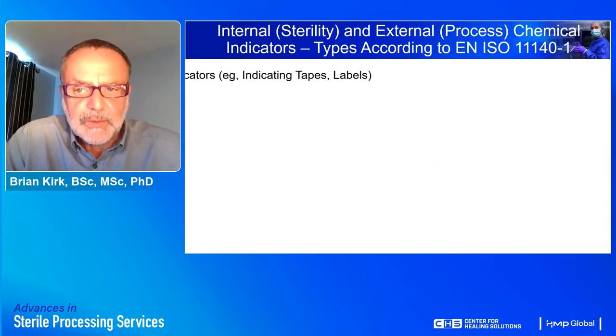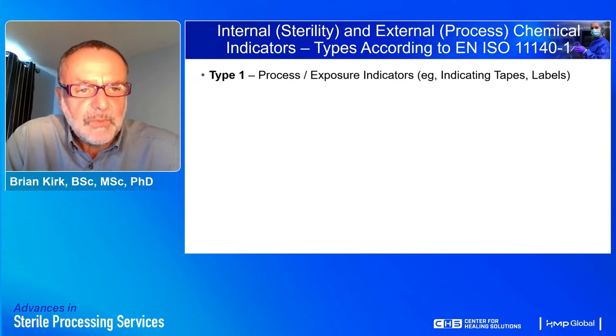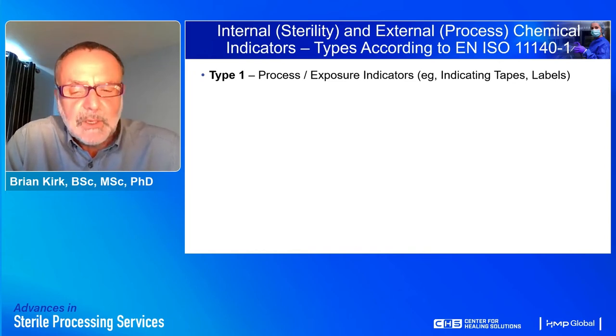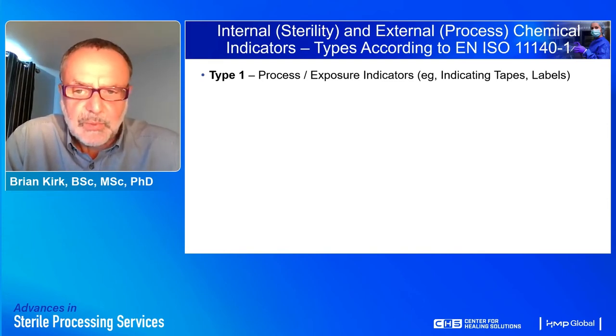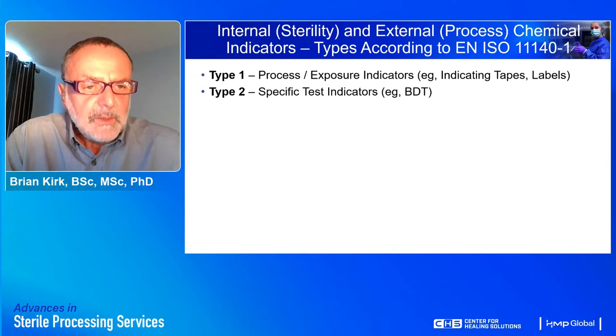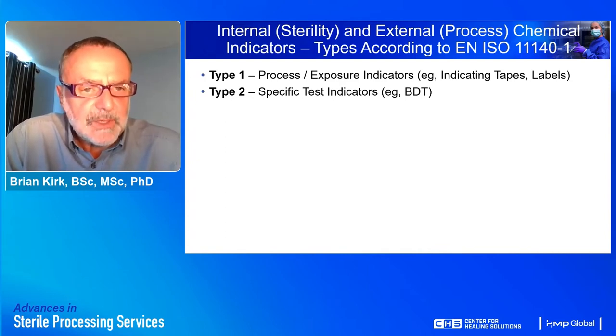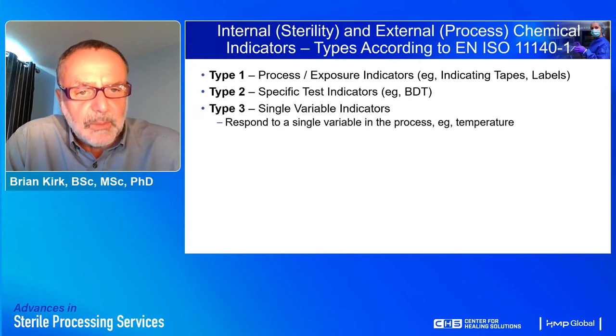Looking at chemical indicators: ISO 11140 Part 1 specifies six categories. Type 1 are process indicators for use on the outside of packs to indicate a pack has been processed. Type 2 are specific test indicators such as the Bowie-Dick test, used on a routine basis to check the sterilizer is working correctly. Type 3 are single variable indicators, which have been around for a long time but offer limited utility because, as their title states, they only monitor one of the process variables.